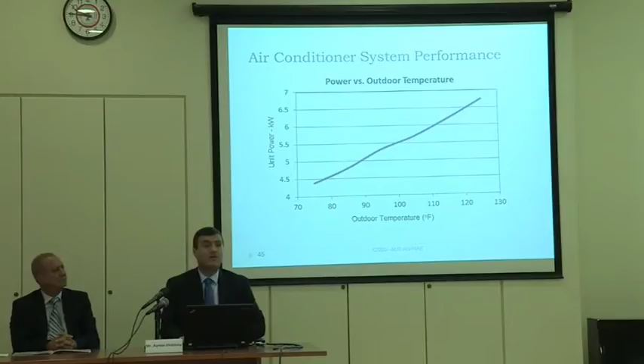Now, not only the cooling capacity, but also the power of the compressor. So here we go. We're losing capacity, and also we need more power for the machines. So we're talking about two different effects: more energy and less cooling capacity. So putting that in the EER value, you can see the EER goes down. When we speak about EER value, for example, at 35, it's going to be different at 46, and we see a big decrease in the EER.